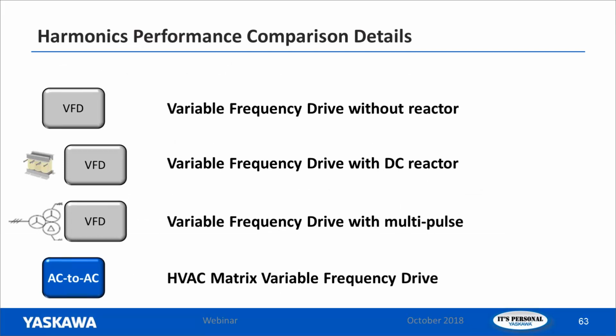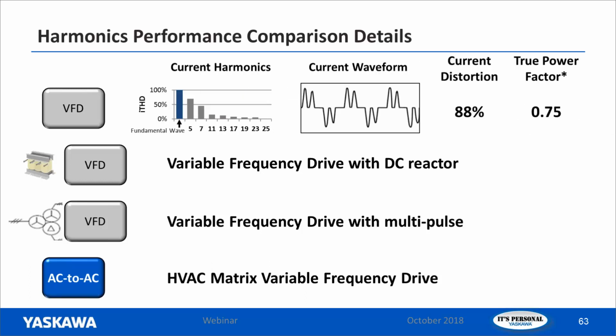We're going to compare 4 of the major harmonic mitigation options. The first one isn't an option at all. We're going to look at what harmonic distortion looks like with just a 6-pulse VFD that doesn't have a DC bus reactor, no harmonic mitigation added whatsoever. What is our starting point? This is what your current waveform looks like, the distortion. A VFD with no harmonic mitigation is going to have up to 88% current distortion with a power factor of 0.75. So what happens if we add a DC bus reactor?